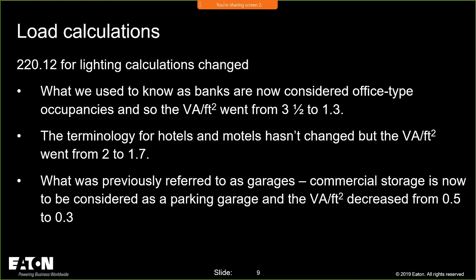the 17 cycle simply referenced 220.12, if I'm not mistaken. I'm just looking to make sure. Yeah. So it says are included in the general lighting load calculations of 220.12. So we separated the 220.14J from 220.12, kept 220.12, especially that table, for non-dwelling units.